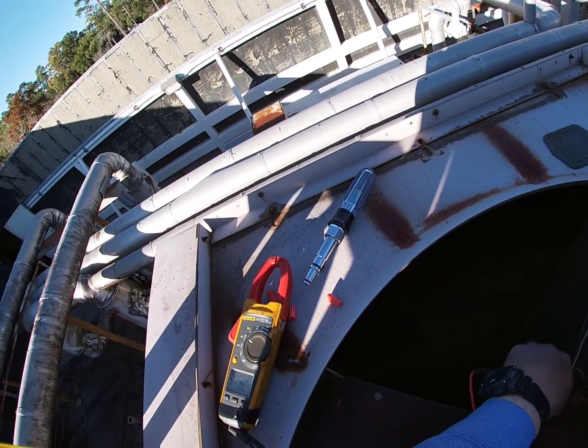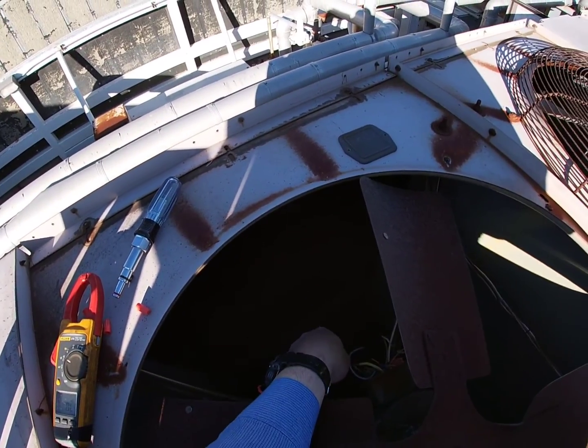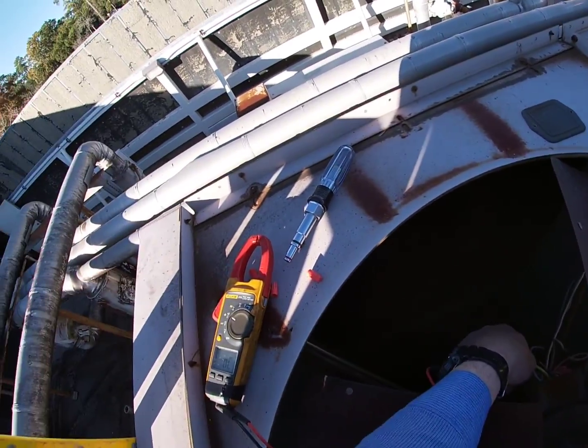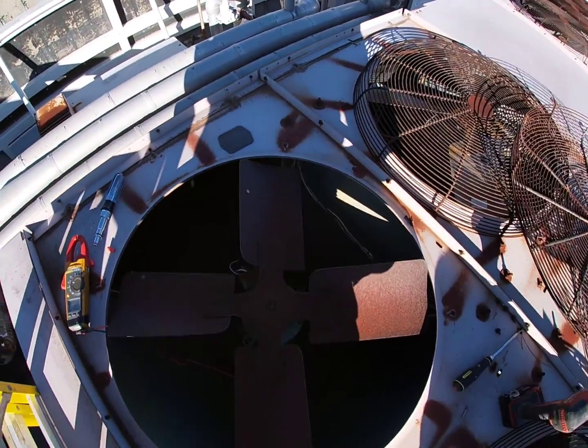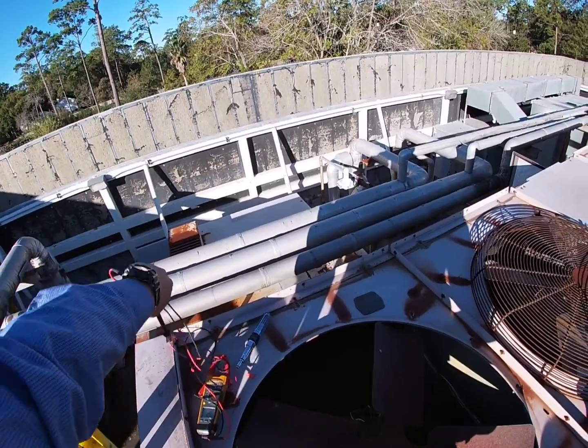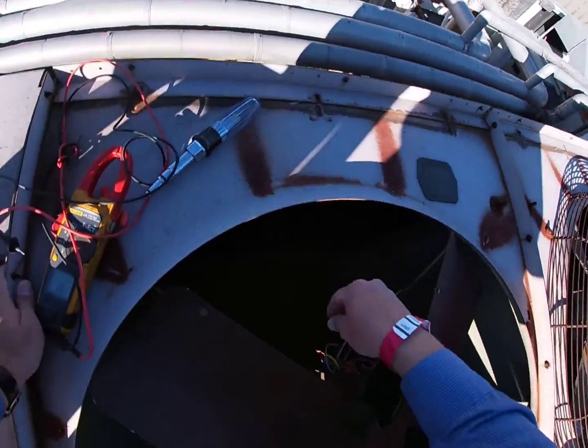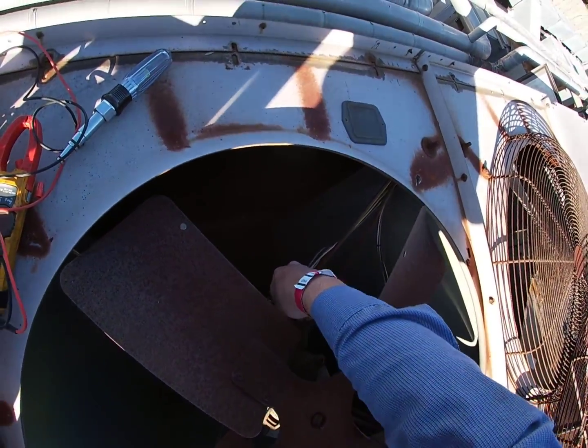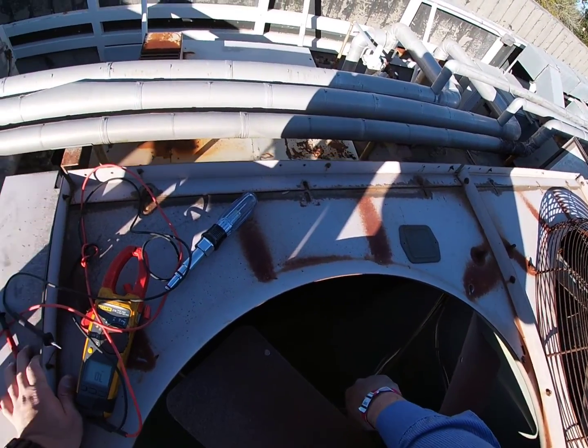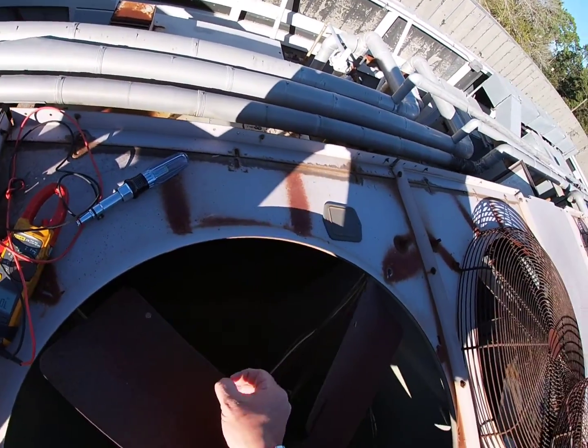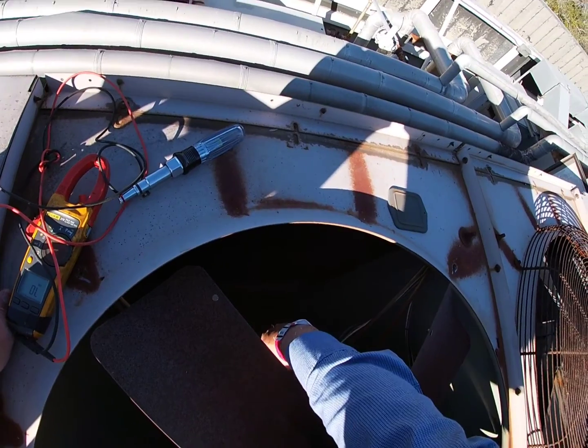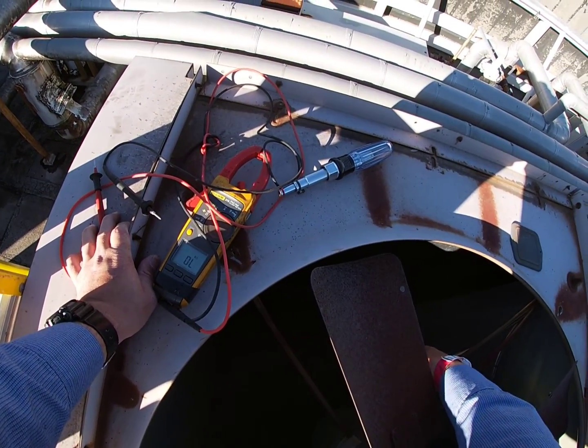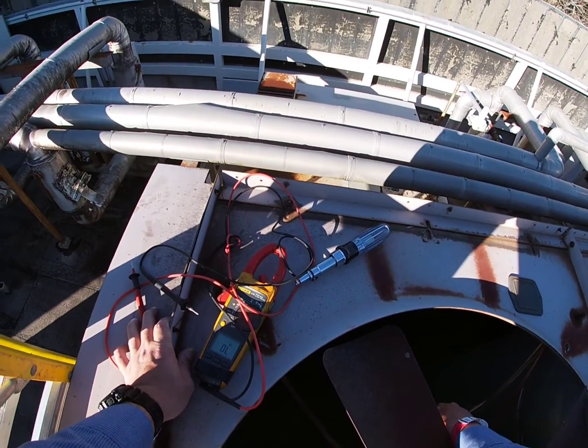Let's check the wire. Wire looks okay, okay, and okay. So we got a bad motor here. We're going to put these wire nuts back on those wires. The main's coming in just in case. I got them disconnected over there, but just to protect anything else here, we'll reset that breaker and run it on test.